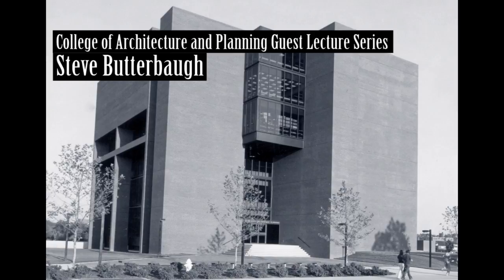Here it is important to understand the building as an integrated system. A big selling point for energy conservation studies lies in the fact that what appears to be obvious, the obvious method of reducing energy consumption, may end up not reducing that consumption. For example, some buildings are designed to lose heat at a specific rate during the winter, and if insulation is pumped into the walls, it may result in the need to cool the building in winter. It depends upon the people and the lights present. Or another example is reduction of lighting levels may require addition of heat to the space through the heating system.